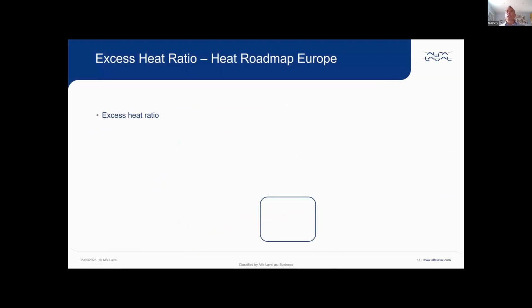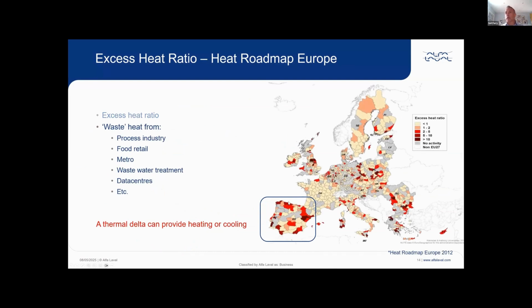So, some more implications to this. I'm using the Heat Roadmap Europe here, and I've focused around Spain, not for any particular reason. I just got some data on that we'll look at in a minute. So this is showing you where the excess heat is across most European countries. And we can see the vast majority of countries have an amount of excess heat. That's available energy that we can use. And if we have a thermal delta, whether it's positive or negative compared to ambient, we can provide heating or cooling. And that's a really important aspect when we start to look at waste heat.